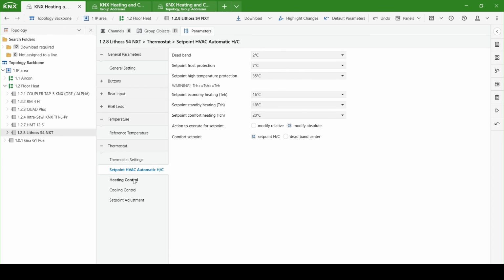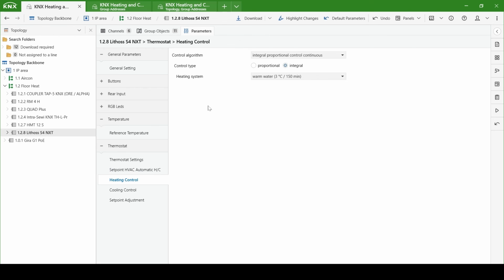Now we have a look at the heating control. So for the heating control here, the type of control we're going to do is integral proportional control, which is continuous. And that means the valve can drive between 0 and 100%. If we were doing electric or something like that, we could use 2-point or pulse width modulation. And depending on your proportional or integral setting, you can choose, you know, it's floor heating, so 5 degrees over 240 minutes.